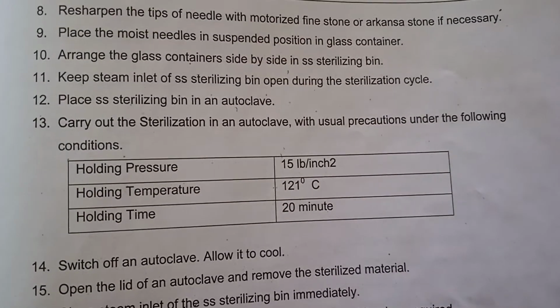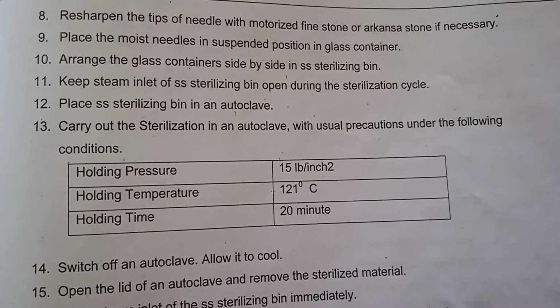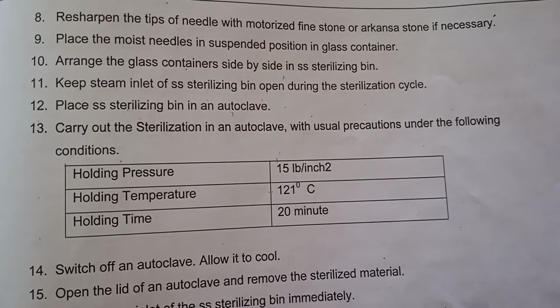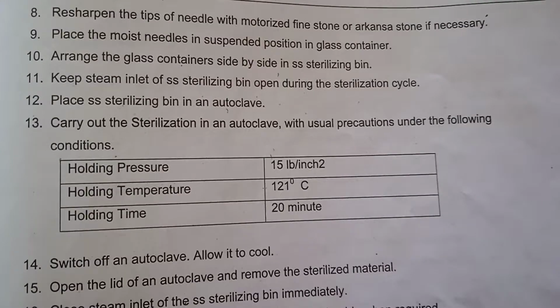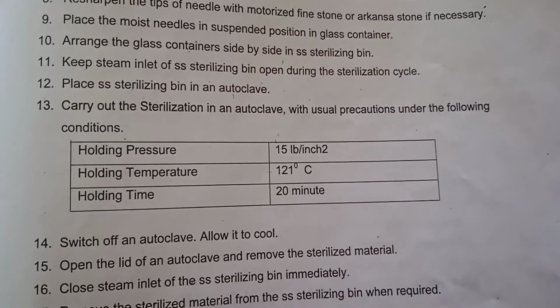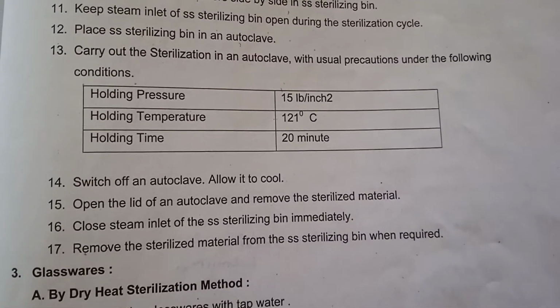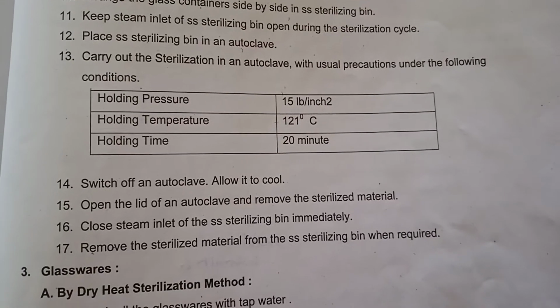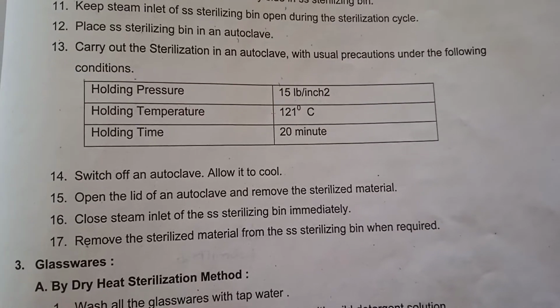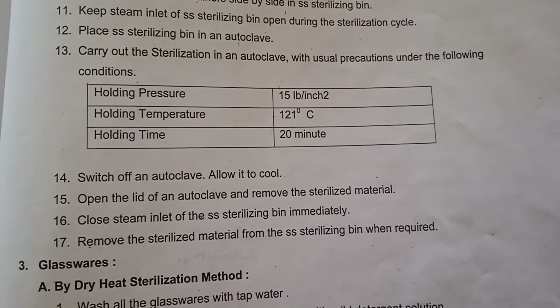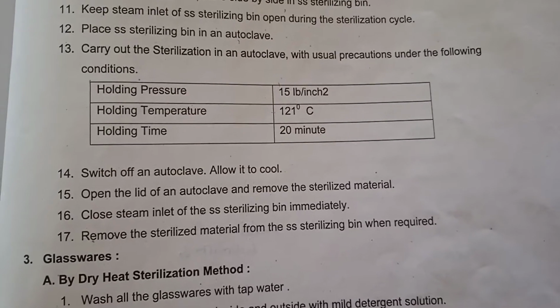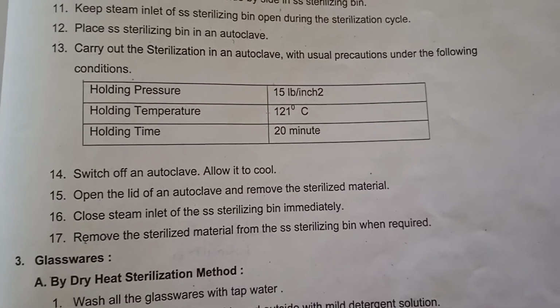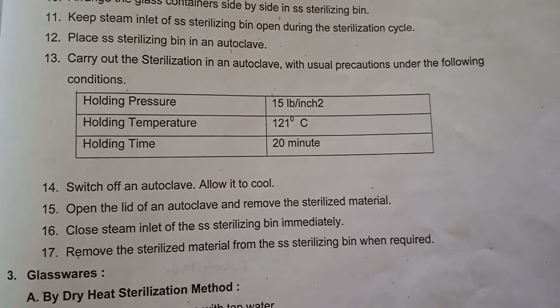Holding pressure will be 15 lbs per square inch. Holding temperature will be 121 degrees Celsius, and holding time is 20 minutes. After 20 minutes, you have to switch off the autoclave and allow it to cool. Then open the lid of the autoclave and remove the sterilized material, and close the steam inlet of the SS sterilizing bin immediately. Remove the sterilized material from the SS sterilizing bin when required.